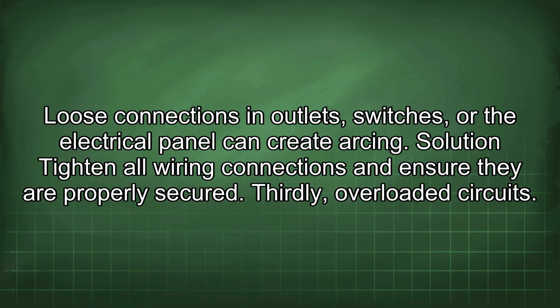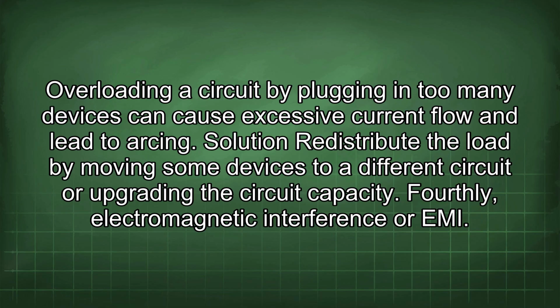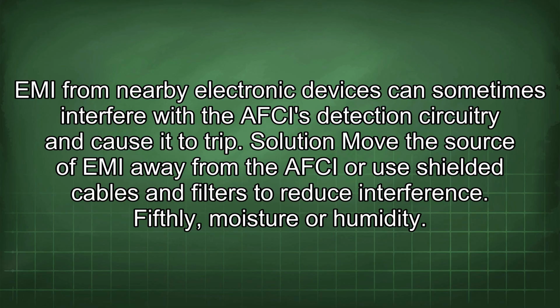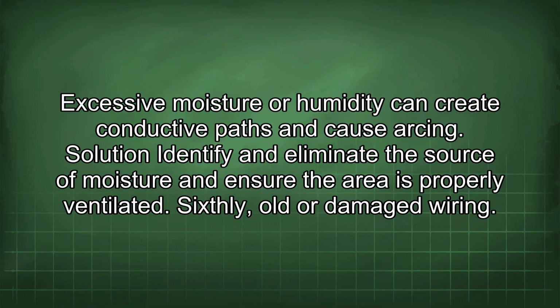Thirdly, overloaded circuits. Overloading a circuit by plugging in too many devices can cause excessive current flow and lead to arcing. Solution: redistribute the load by moving some devices to a different circuit or upgrading the circuit capacity. Fourthly, electromagnetic interference, or EMI. EMI from nearby electronic devices can sometimes interfere with the AFCI's detection circuitry and cause it to trip. Solution: move the source of EMI away from the AFCI or use shielded cables and filters to reduce interference.